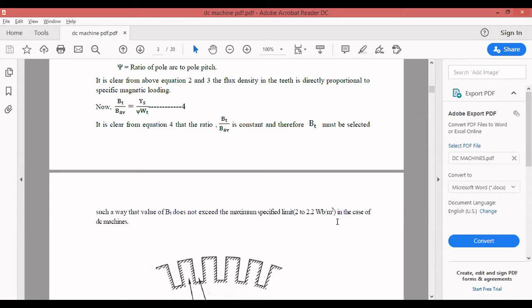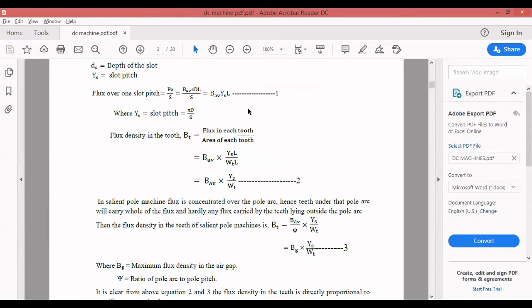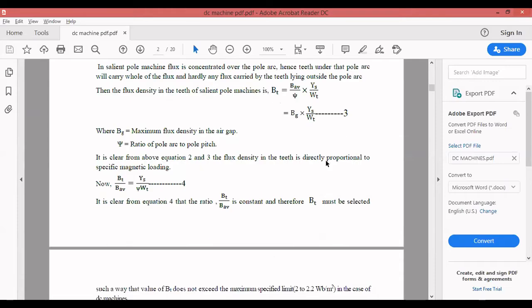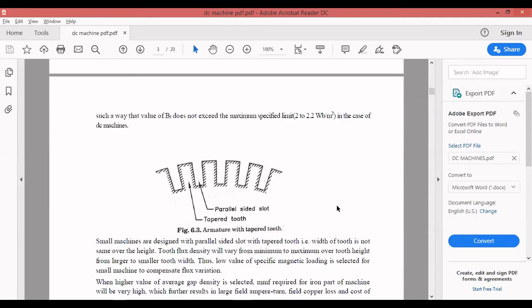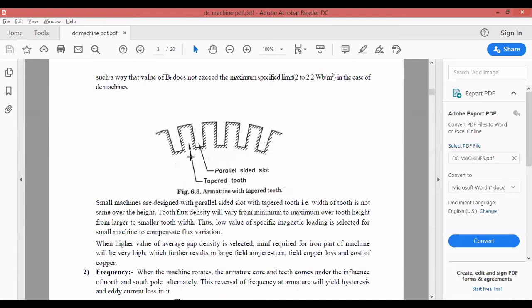The second factor influencing the selection of specific magnetic loading is frequency. When the armature rotates, the armature core and teeth come under the influence of north and south poles alternately. This reversal of frequency at the armature will yield hysteresis and eddy current losses. When armature rotates, it comes under the south pole and then the north pole, causing a reversal of magnetic lines.